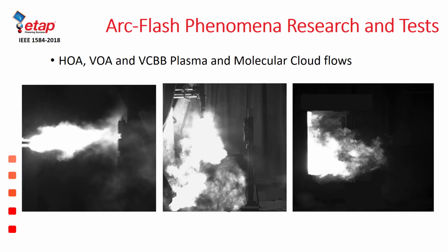On the right, we see an image of an enclosure already engulfed in an arc flash event. This configuration is meant to be the vertical conductor in a box configuration. And as we can see, the plasma is mostly concentrated towards the bottom of the enclosure. Because of the barrier effect, the columns, the gases, the molecular cloud all get concentrated and ejected out tangentially away from the electrode plane. This would cause a higher amount of energy transfer towards the calorimeter placed in front.